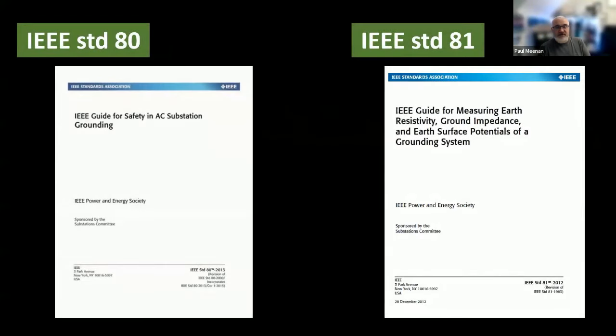If you wanted to look further afield, there is IEEE Standard 80 in America, in parts of America, which is a guide for safety in substation grounding. Grounding is very similar to earthing. There is also the IEEE guide for measuring earth resistivity. These are some very good standards. Standard 81 from the IEEE, if you want to further research the subject, if you're writing your own papers about the effects of energy dissipation and good earthing or bad earthing.